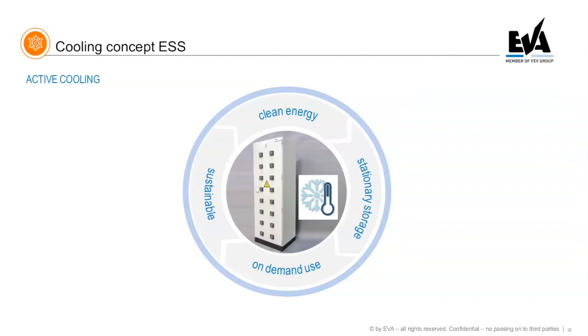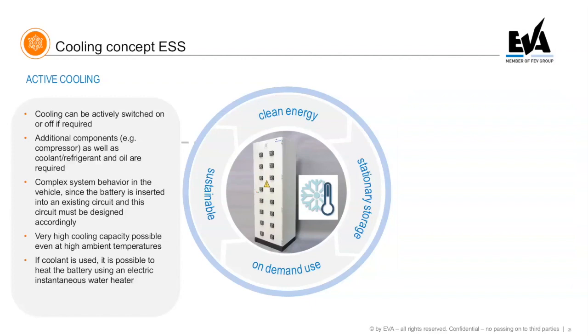Let's look at active cooling. With active cooling you have the big advantage that you can actively switch it on and off as required. It depends on how you realize it, with fans or coolant, but either way you need additional components, such as fans, compressors, as well as coolant or refrigerant. This is something you have to consider in the early concept phase and design of the battery system.